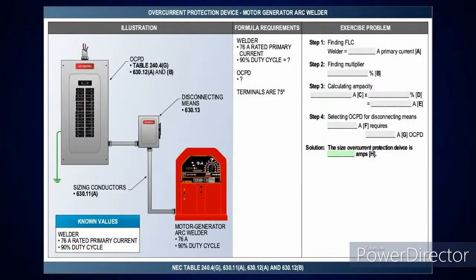Then when you come over here, you pick up a motor generator arc welder. So we've got you an easy calculation. You know the welder, looking at this, it's 76 amps, and we're just going to get the percentage. I'm going to look at 630.12 A and B there. You're going to know to take it at 200%. Don't exceed the calculated value, and drop down to the next standard size, for your homework next week.